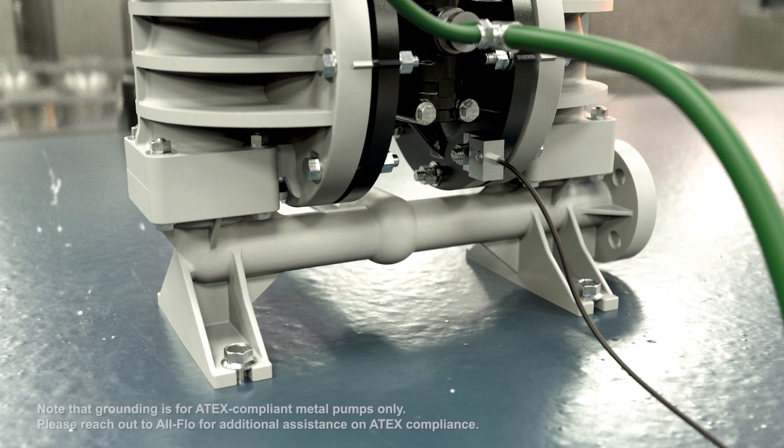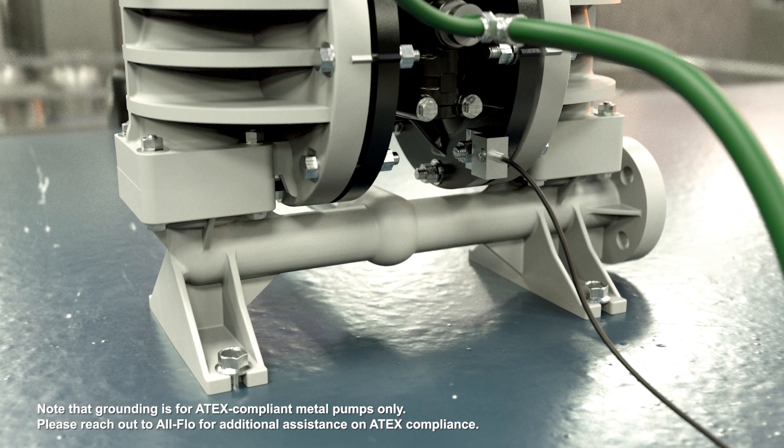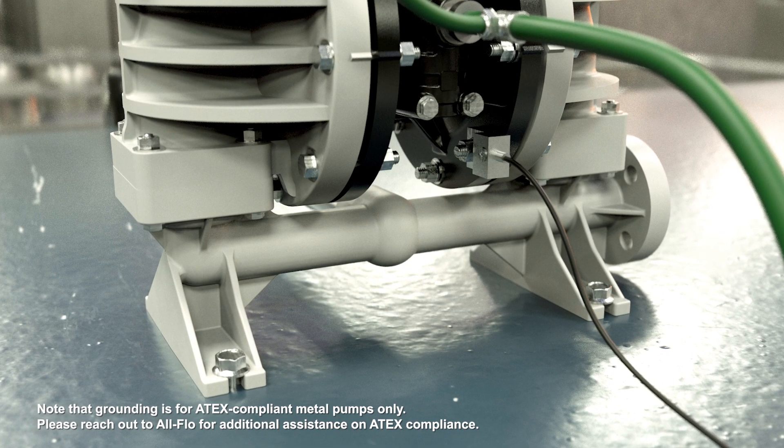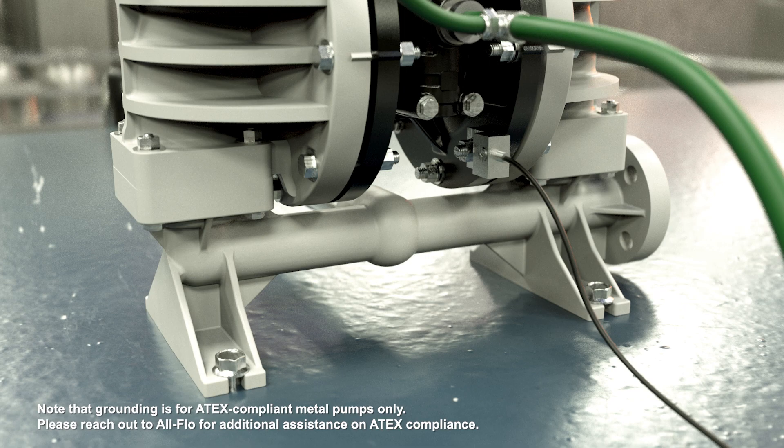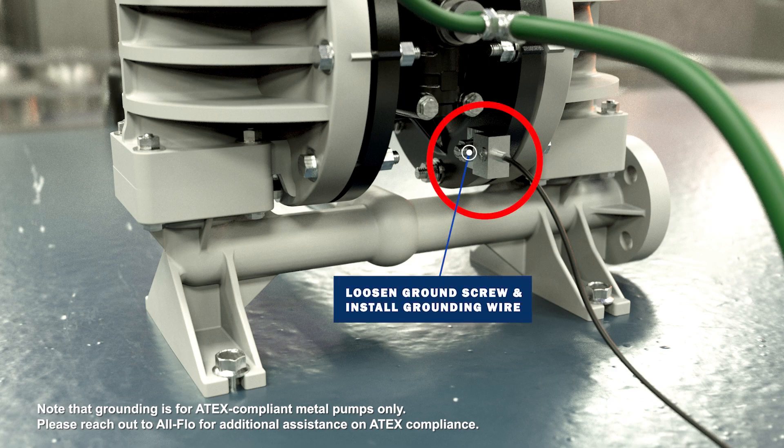For applications that handle flammable fluids and or wherever static electricity is a hazard, the pump as well as the surrounding equipment must be properly grounded. To ground the pump, loosen the grounding screw and install a grounding wire. Tighten the grounding screw.